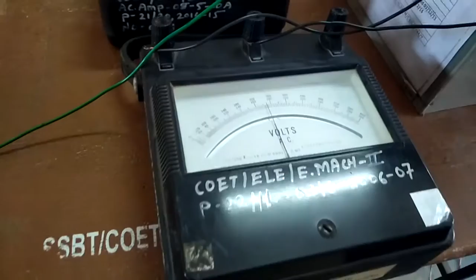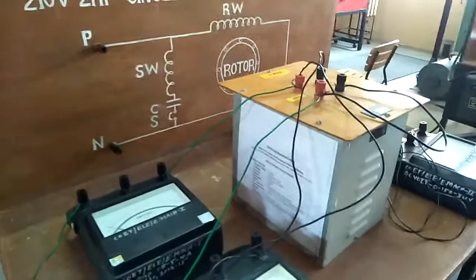So 345 means 230 plus 115. This means the voltmeter connected between these two terminals is measuring the additive voltage, hence these two terminals are not in identical polarity, they have different polarity. So this is the polarity test.